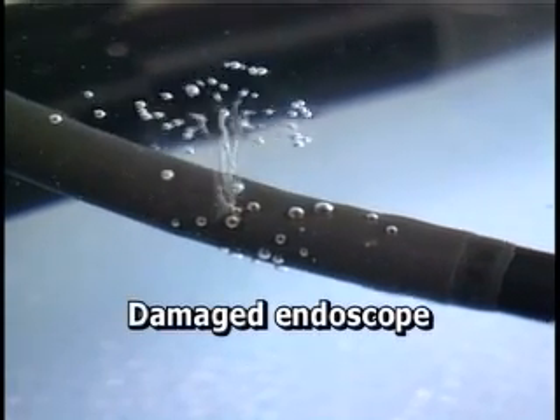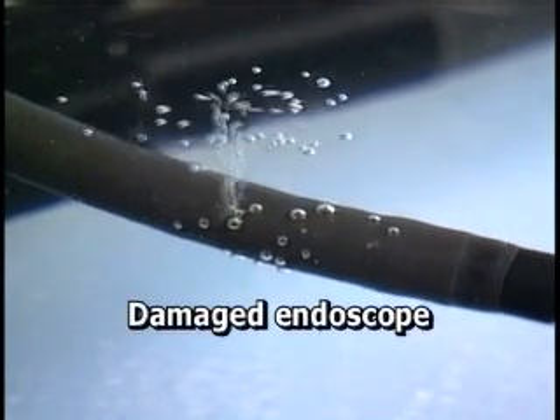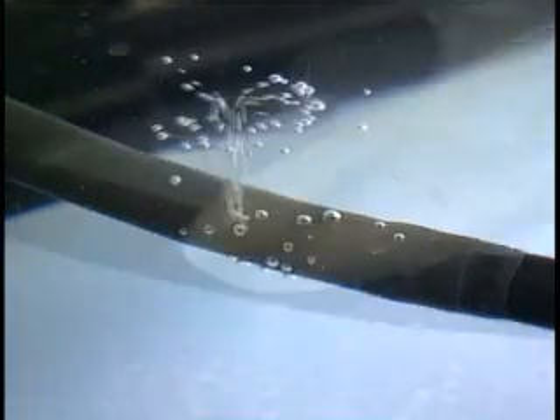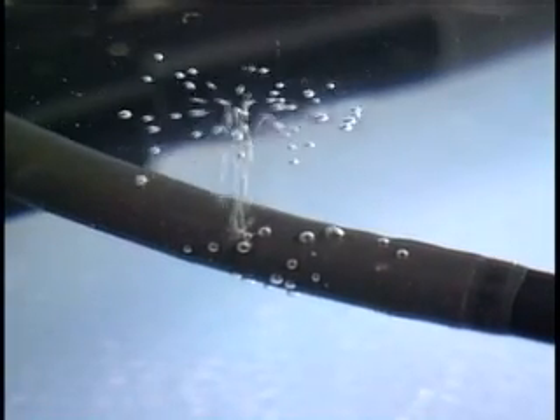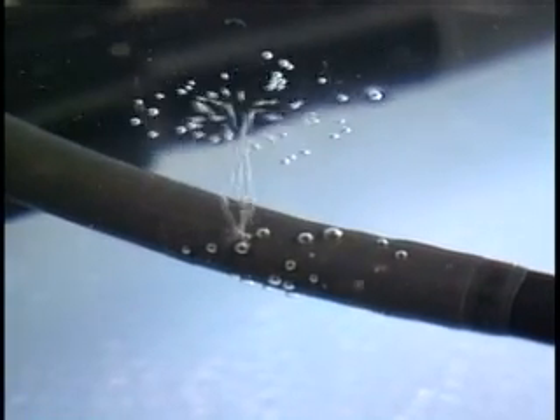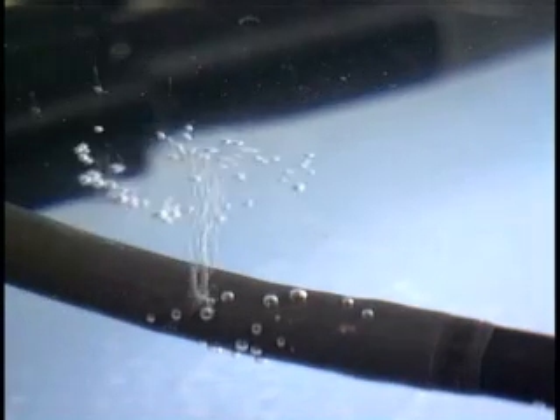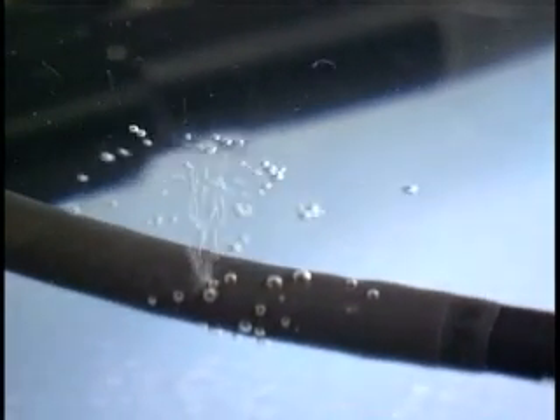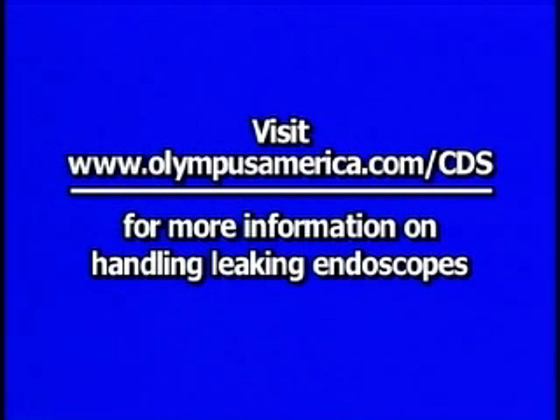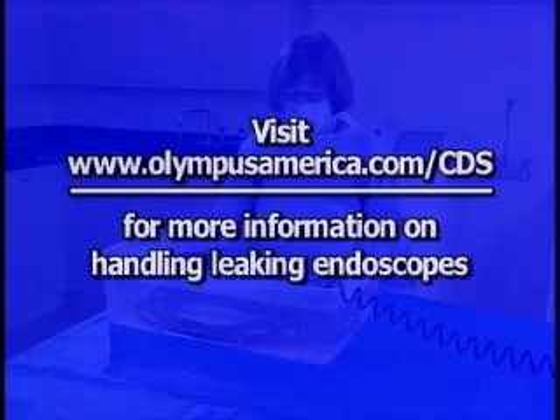Leaks like this will allow fluids to penetrate and damage the endoscope. If you observe such a leak, do not turn the air supply off. Rather, remove the endoscope from the water, blow out the channels with air, and dry the endoscope prior to turning off the leakage tester. Contact Olympus for instructions on how to reprocess a leaking endoscope prior to sending the endoscope to Olympus for repair.